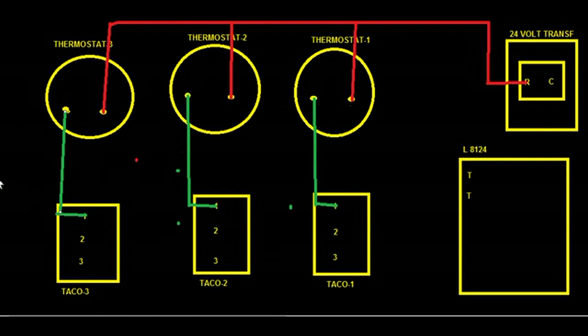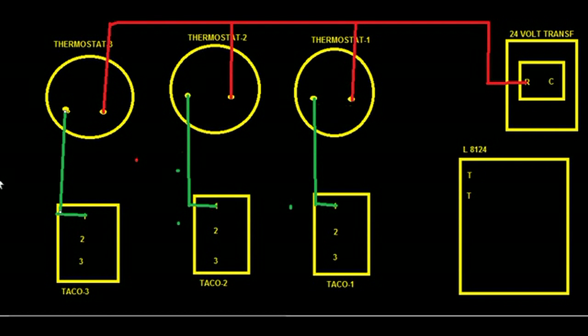This is a typical hydronic system working with 24 volt. We're doing a circuit layout of how this hydronic system is wired. The common wire, we're coming over here, you see the common one goes back to the transformer, the 24-volt transformer.